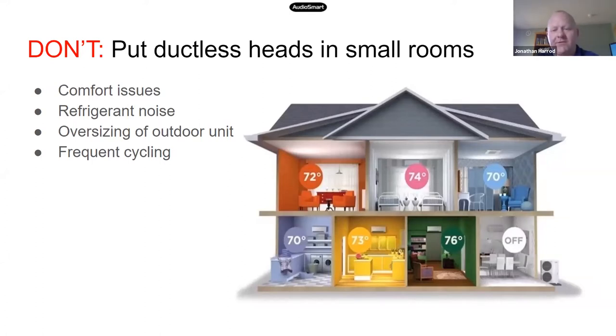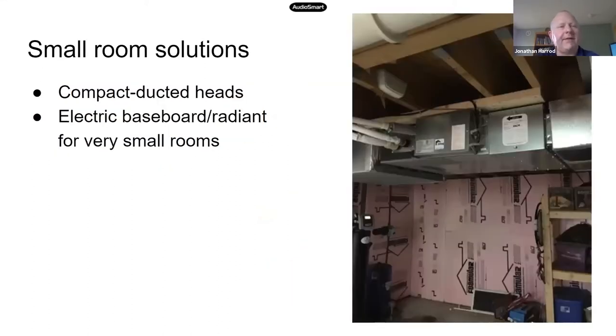One of the ways that manufacturers get around this is that if, say, this laundry room is only calling for 3,000 BTUs, but the outdoor unit can only modulate down to 8,000, those would be pretty typical numbers, the outdoor unit has to bleed refrigerant through the other heads, and that can create unexpected hissing noises that can wake people up in the night. It can also mean that you're putting heating or cooling into rooms where you don't want it. So we want to avoid this practice of putting heads in every room. There are some ways that we can get around that. A couple solutions that we frequently use.